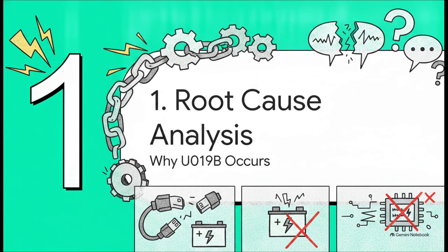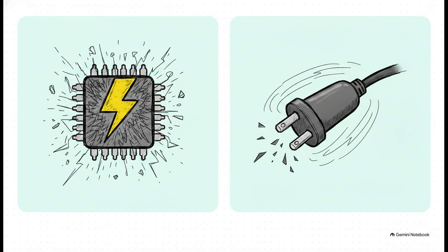Okay, so how do we end up in that terrifying situation in the first place? Let's break down the root causes. The U019B fault usually boils down to two main culprits, electrical or physical. On the electrical side, you've got electrical overstress, EOS, and electrostatic discharge, ESD. Basically, the exact second you plug in that charging gun or those high-voltage contactors close, you can get these massive nanosecond-level voltage spikes. If your front-end protection isn't bulletproof, these surges will literally fry the communication chips or CAN transceivers, causing a permanent hardware open circuit.